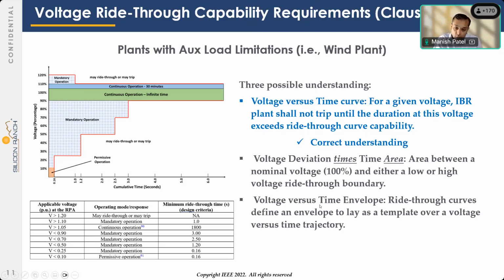This is not a voltage versus time envelope so that you can have an actual event, say, recorded by a DFR. You take that trace, you overlay it on top of this curve and decide if the plant was able to ride through or not, right? So the standard goes and tries to clarify all this.